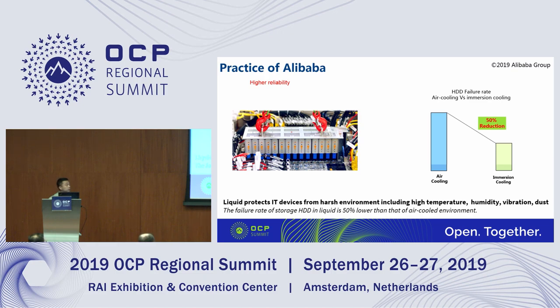The IT device is completely immersed in a dielectric fluid, thus completely isolated from the air. Liquid can protect the IT device from harsh environments. Compared with air cooling, immersion cooling eliminates humidity, vibration, dust, and other failure factors of electronic equipment. Through nearly one year of large-scale operation, we found that the failure rate of storage HDD in liquid is about 50% lower than that in an air-cooled environment. So immersion cooling can help IT devices get higher reliability.